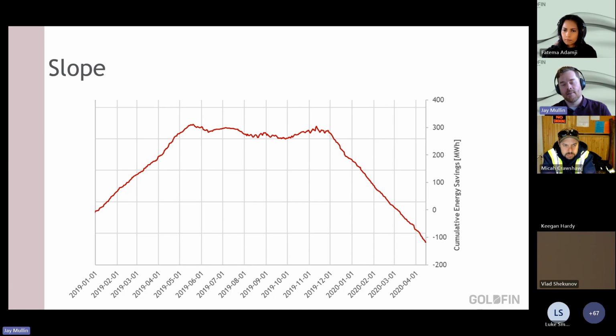The next thing that's important to look at on your CUSUM is the slope. A straight line in any direction means consistent energy use - not necessarily the absolute values, but consistent energy intensity relative to heating degree days, cooling degree days, occupancy, whatever's built into the model relative to those independent variables.